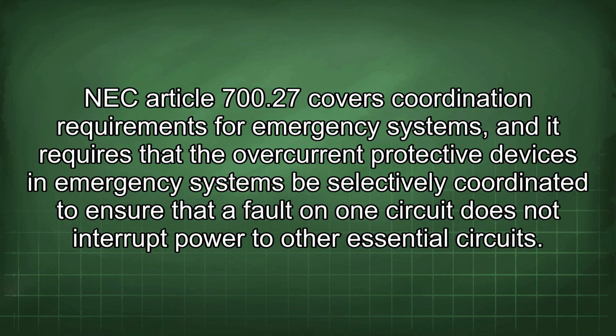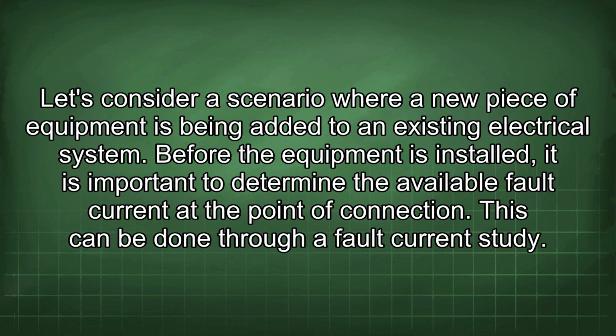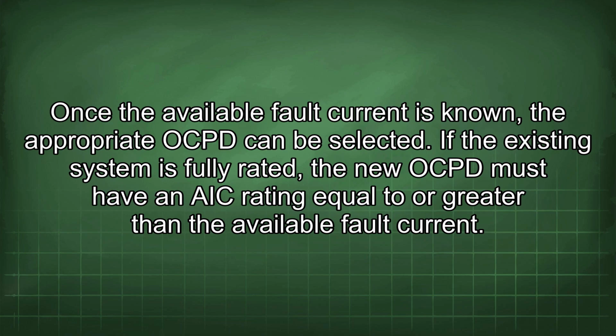essential circuits. Let's consider a scenario where a new piece of equipment is being added to an existing electrical system. Before the equipment is installed, it is important to determine the available fault current at the point of connection. This can be done through a fault current study. Once the available fault current is known, the appropriate OCPD can be selected.